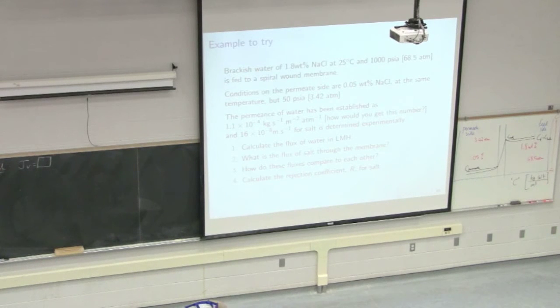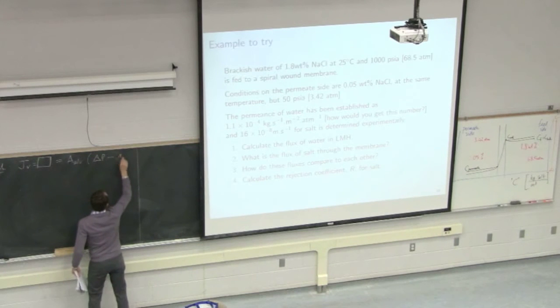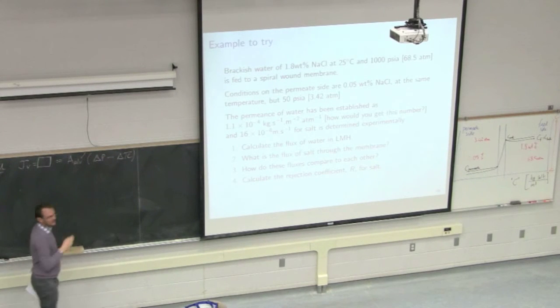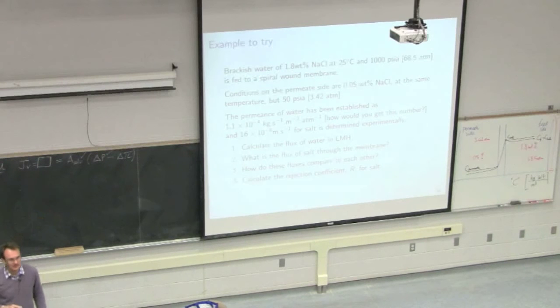The first goal is fairly obvious: calculate the flux of water in LMH. The plan is deceptively simple — we use J_V equals A_solvent times (delta P minus delta pi). We're given A_solvent as 1.1×10⁻⁴. We have enough information for delta P, and we have what we need for delta pi. The only part needing a little extra work is delta pi, since delta pi equals pi_feed minus pi_permeate.